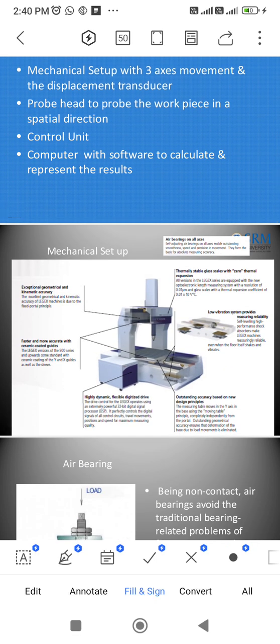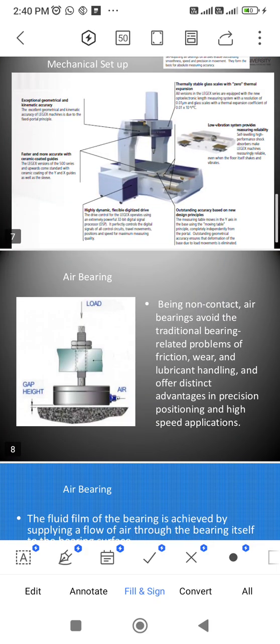So this is the mechanical setup. This setup provides a rigid frame that allows motion along the X, Y and Z axis. To ensure the smooth and precision motion, some air bearings are used. These bearings are reducing friction and wear, allowing the probe to move quickly and accurately. So air bearing is working by creating a thin film of compressed air between surfaces. This means there is virtually no contact, so the movement is frictionless, and it also ensures that pressure is evenly distributed, which is critical for maintaining precision.